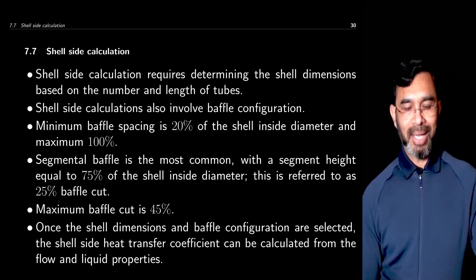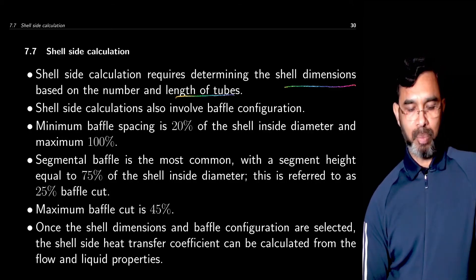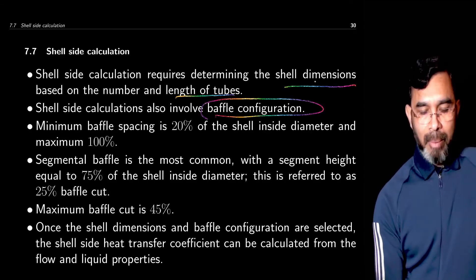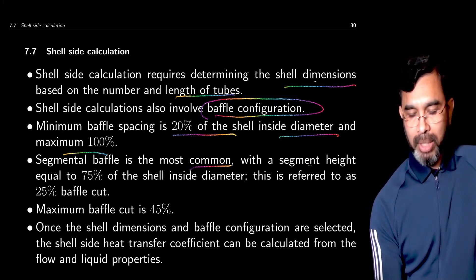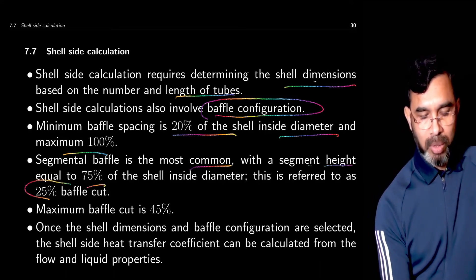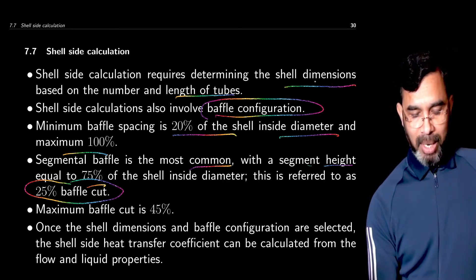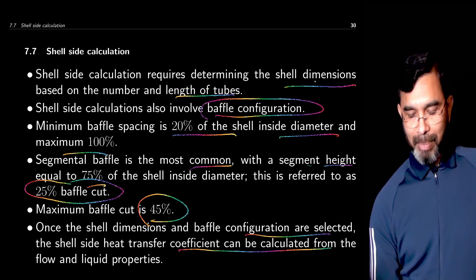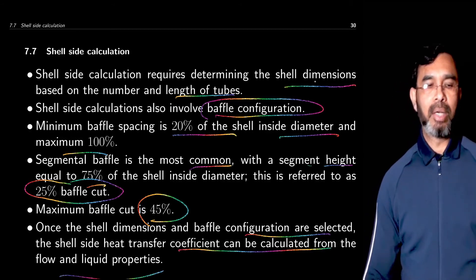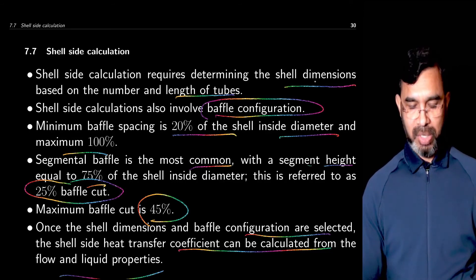You also need to calculate the heat transfer area for the shell side. For that, you determine the shell dimensions based on the number and length of tubes. Shell side calculations also involve the baffle configuration. Minimum baffle spacing is 20% of the shell inside diameter and maximum is 100%. Segmental baffles are most common, with a segment height of 75%, referred to as 25% baffle cut — meaning 25% of the shell diameter remains open. Maximum baffle cut is 45%.